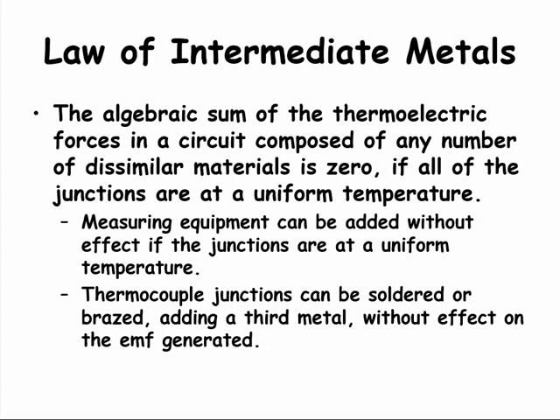The second law, the law of intermediate metals, states that if we have intermediate metals and multiple dissimilar metal junctions, the EMFs may sum to zero if all the intermediate junctions are at the same temperature. So we can add equipment to the circuit, and as long as all of the equipment junctions are at the same temperature, the total EMF is zero and does not affect the measured EMF. A second consequence is that we can use solder to make thermocouple junctions, and the third metal does not affect the EMF generated. This makes it easy to make junctions in the field using normal soldering techniques.